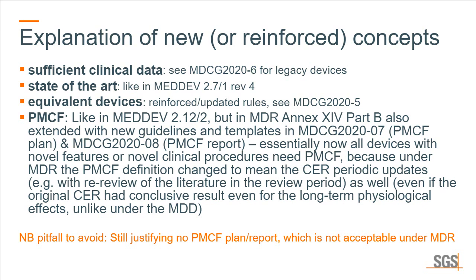The PMCF was typically needed if some of the clinical data was inconclusive and we didn't know the full effect of the device on the patients for the full technical lifetime. Then, and usually only then, we needed post-market clinical follow-up. But for devices where we already knew the full physiological effect over the lifetime of the product, this was usually not needed. Now the post-market clinical follow-up also includes the periodic update of the clinical evaluation report, and in that sense, post-market clinical follow-up is typically needed for all types of medical devices.